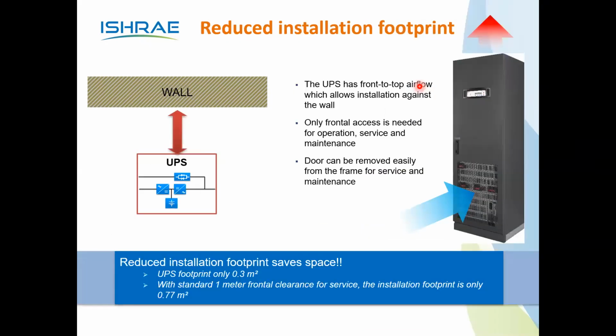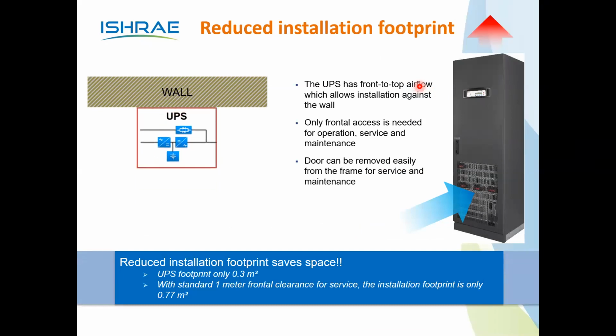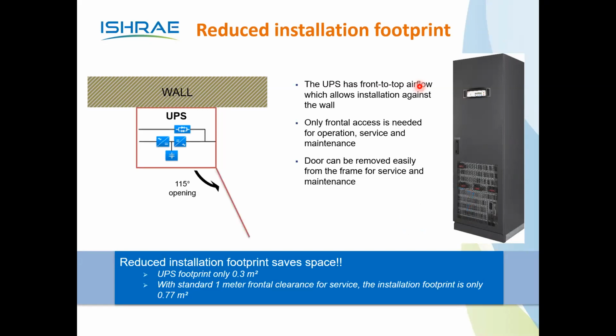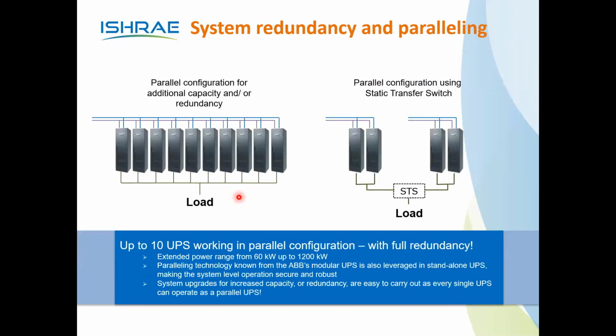Another main important point: the air exit is at the top, so the UPS can be kept close to the wall. It's a big money saving on account of space and front service, as well as unity power factor and transformerless topology. Another main important point is flexible battery management. We just need space to open the door on the front side. It can come in various configurations, standalone as well as parallel redundant.